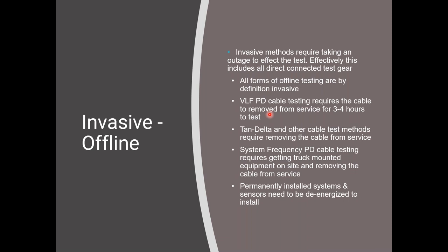Your VLF, your tan delta, are forms of it. They require a cable removed. VLF requires the cable removed from service. And we'll look at the connections in a bit, but you isolate the cables, connect your test sets up, and you run a test. One of the things with VLF or the tan delta test, since you're using that 0.1 hertz as your common frequency, it's a long-term test. So it could take two to four hours to run your test. And over that time, you've got your low frequency, but you're creeping your voltage up.